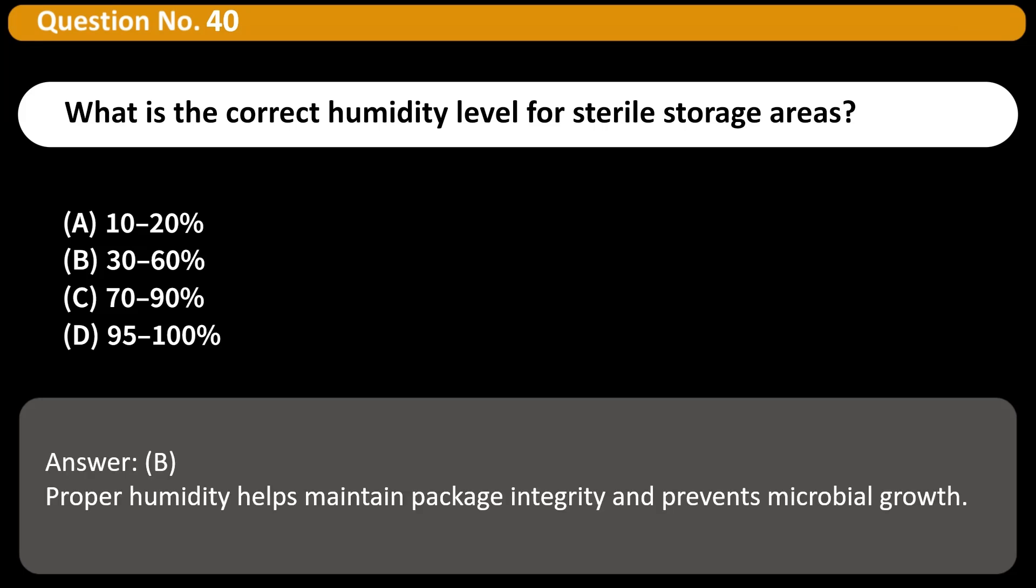What is the correct humidity level for sterile storage areas? A. 10 to 20%, B. 30 to 60%, C. 70 to 90%, D. 95 to 100%. Answer B. Proper humidity helps maintain package integrity and prevents microbial growth.